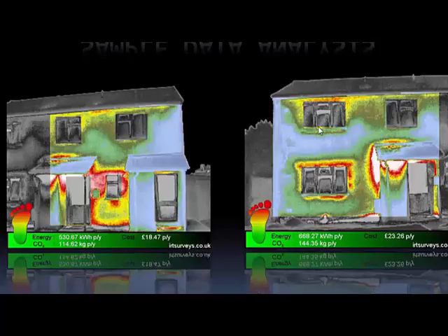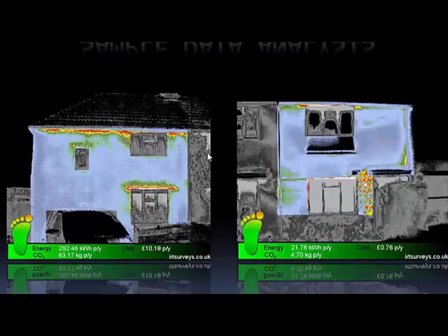It's not all bad news. You can actually pick all your properties that are well insulated. Here we can see these properties are nice and consistent on the walls. The software hasn't picked out any regions of big interest. Depending on the construction, there will always be bits of additional heat loss at the eaves details, and there will always be bits of thermal bridging.